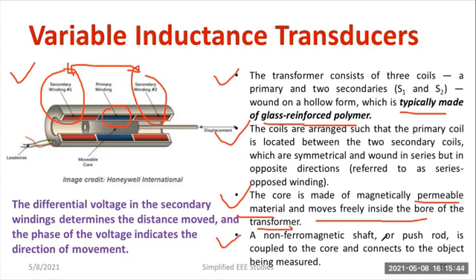A non-ferromagnetic shaft or push rod is coupled to the core and connected to the object being measured. This mechanical part is connected to the shaft or core of the particular LVDT, where you are supposed to measure the displacement position of that particular object. That is the ultimate goal, meaning the object is directly connected to that particular core.